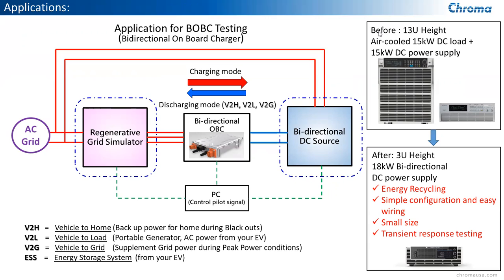Typically, to test this, you would have to use a very large independent DC conventional load. You'd also need a separate DC source in order to use it as a source when it's working bidirectionally. Now with our product being in this nice compact 3U package at 18 kilowatts, you can do all of that with one unit. It gives you the ability to act as a battery when the charger is charging it, and it will simulate that battery perfectly, and we'll go into that in a little more detail in another slide. It'll also be able to act as a source and put power back to the onboard charger that's bidirectional, so that power can then be put back out to the grid.